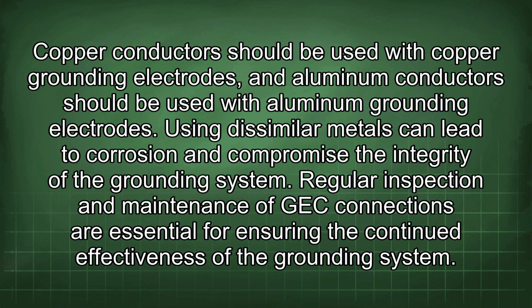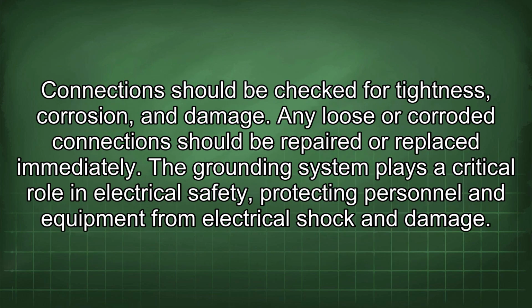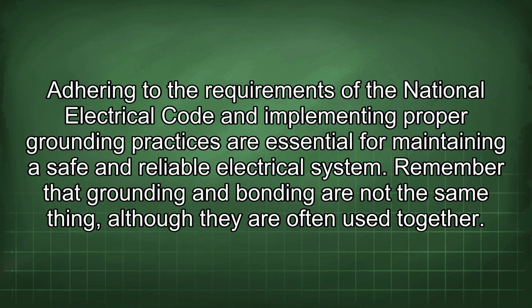Regular inspection and maintenance of GEC connections are essential for ensuring the continued effectiveness of the grounding system. Connections should be checked for tightness, corrosion, and damage. Any loose or corroded connection should be repaired or replaced immediately. The grounding system plays a critical role in electrical safety, protecting personnel and equipment from electrical shock and damage.